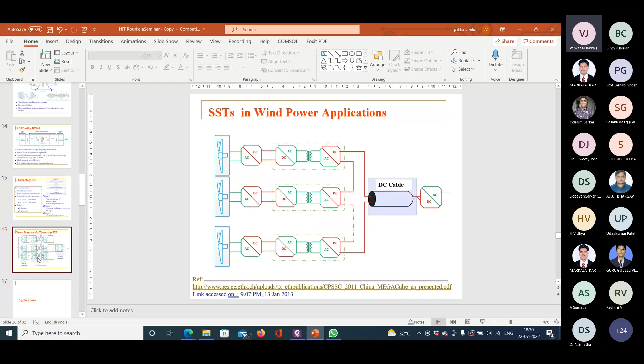So where is it? Yeah, here, this has a lot of capacitors, and on the primary side there aren't many, but inductors are there. And there's an issue: when there is no charge across your DC link capacitor and you directly connect to the grid, you will see a huge inrush current, which can damage the switching devices.